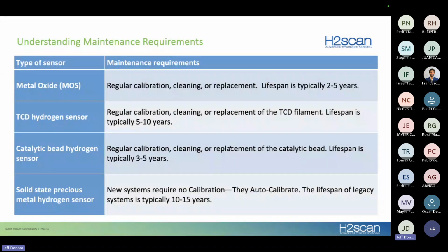And of course, when you talk about maintaining these systems, this is what customers typically complain about the most: what do they have to do to the sensor. In battery systems, this is where it's important to match the right sensor with the battery system. Let's say you have a valve regulated battery that has a lifespan of 3 to 5 years. That's typically not a problem with any of these technologies, because your metal oxide, your MOS sensor, or your catalytic bead sensor can last 3 to 5 years before you have to start replacing parts. TCD sensors typically last 5 years in most battery applications. So that sort of sensor can match that battery type quite well.